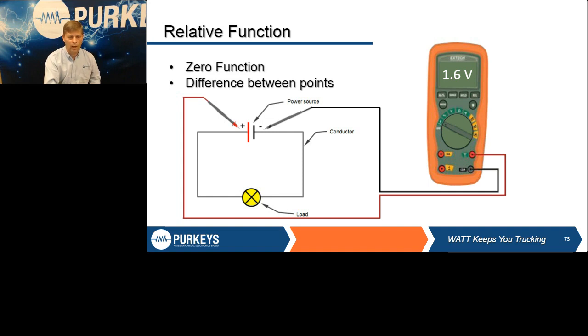So, for example, you're checking a taillight circuit. You can put it across it and zero it out at 0 volts, and then see, if you added another light to it, what did that do to your voltage supply? Blower motor, see what it does under different settings. You start off with it at 0 with it on low, you crank it up, and whatever that number displays is telling you how much drop or change there is in that circuit.